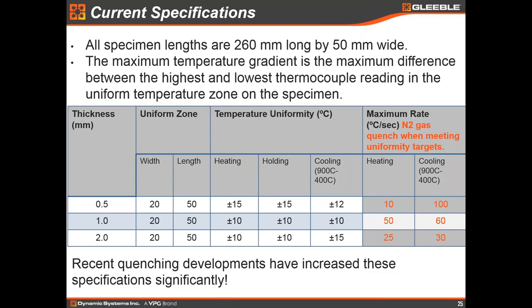The published specifications for the two-inch / 50 mm strip annealing setup in a standard Gleeble include temperature uniformity specifications for the uniform zone, with the system supporting thicknesses from 0.5 mm to 2 mm. The maximum cooling rate using nitrogen gas is noted in the specs. Recently, work has been done on high-flow helium which gives much better cooling rates, and those improved specs will be published soon for those interested in advanced high strength steels requiring faster cooling.